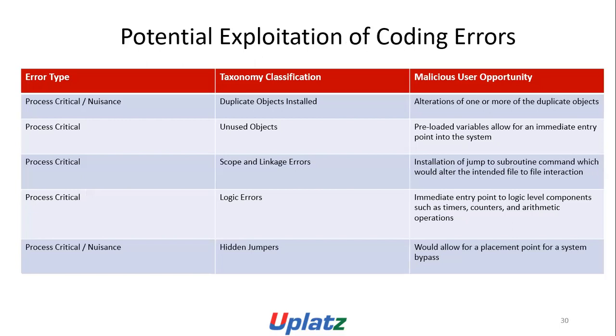Potential exploitation of coding errors. Error type: process critical, nuisance. Taxonomic classification: duplicate object installed. Malicious user opportunity: alteration of one or more of the duplicate objects. Error type: process critical. Taxonomic classification: unused objects. Malicious user opportunity: preloaded variables allow for an immediate entry point into the system. Error type: process critical. Taxonomic classification: scope and linkage errors. Malicious user opportunity: installation of a jump to subroutines command, which would alter the intended file-to-file interaction. Error type: process critical. Taxonomic classification: logical errors. Malicious user opportunity: immediate entry point to logic level components such as timers, counters, and arithmetic operations. Error type: process critical, nuisance. Taxonomic classification: hidden jumpers. Malicious user opportunity: a placement point for a system bypass.